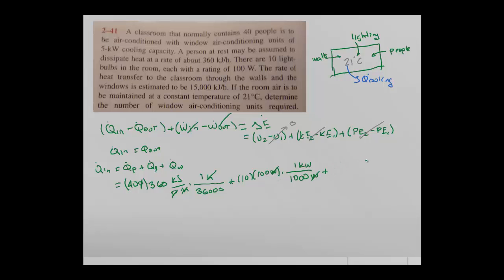Finally, we get the heat estimate through the walls and windows, which we have been told is 15,000 kJ per hour. Similar to before, one hour is 3600 seconds, giving us kilowatts. Adding all contributions together, we get 9.17 kilowatts total Q_in.